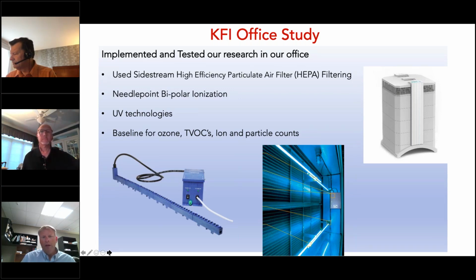So we use side stream portable HEPA filter fan filter units, because we had a heat pump system that couldn't withstand any more filtration than what we had in there, which was about a MERV 8. So we put in 9 different portable fan filter units with HEPA filters across the building, including in some mechanical rooms that had a common return. We did put in needlepoint bipolar ionization, and we tested about 4 different manufacturers of bipolar ionization. We already had UV technologies in some of our air handlers, the main air handler that brings in outside air. And then we did our baseline testing for ozone, TVOCs, ions, and particle counts.